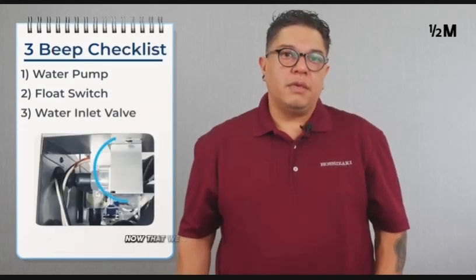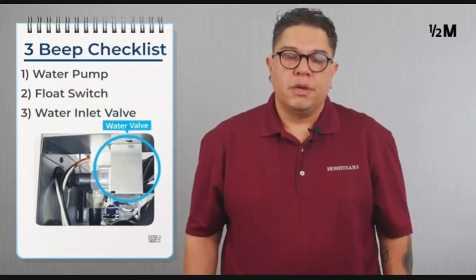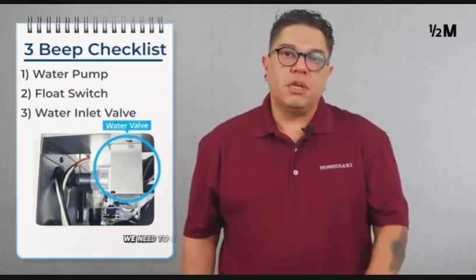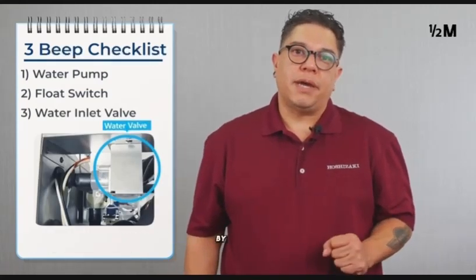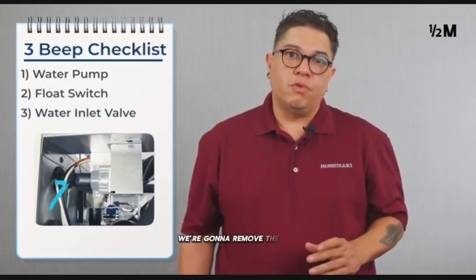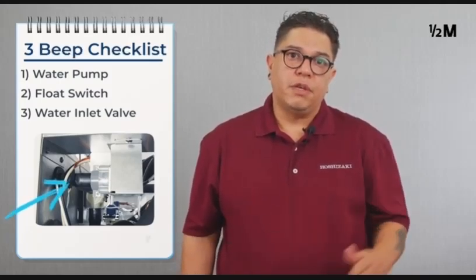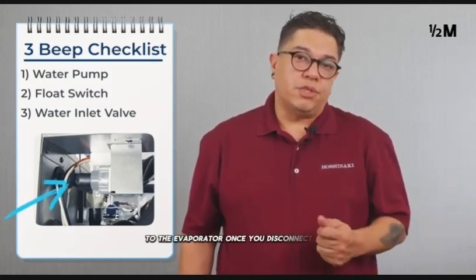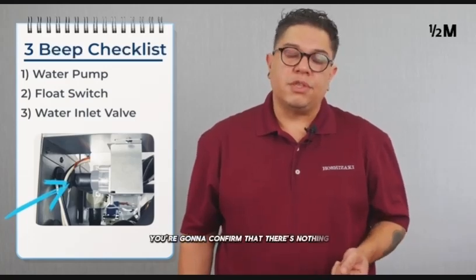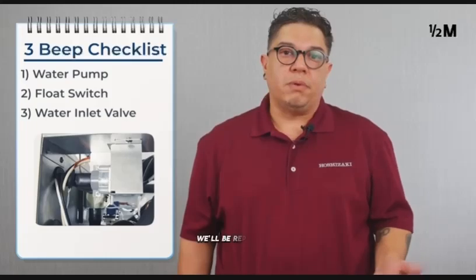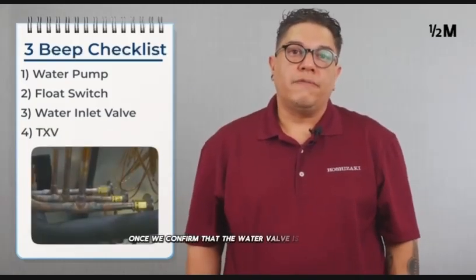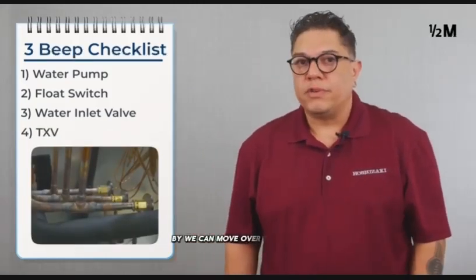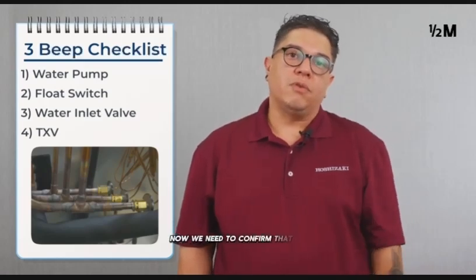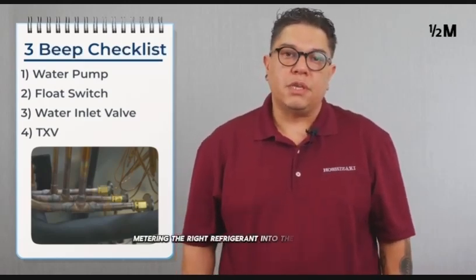Now that we confirm that the float switch is working, we're going to move over to the water valve. We need to confirm that the water valve is not leaking by. The way that we're going to do this is we're going to shut the machine off. We're going to remove the hose that runs from the water valve to the evaporator. Once you disconnect that, you're going to confirm that there's nothing steadily coming out of the water valve. If the water valve is leaking, we'll be replacing it. Once we confirm that the water valve is not leaking by, we can move over to the TXV. Now we need to confirm that it's metering the right refrigerant into the evaporator.